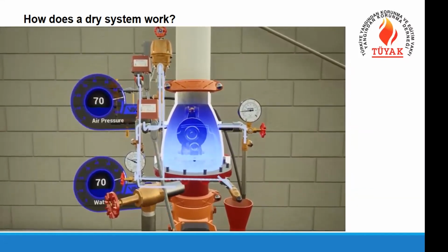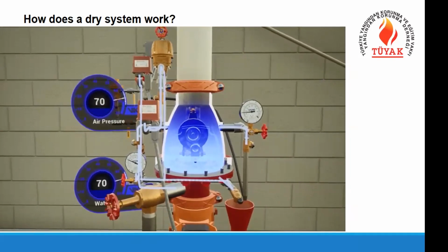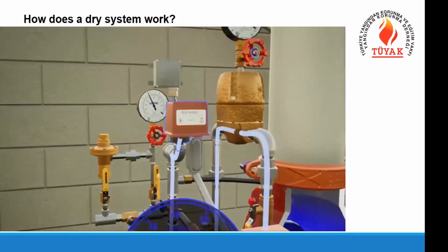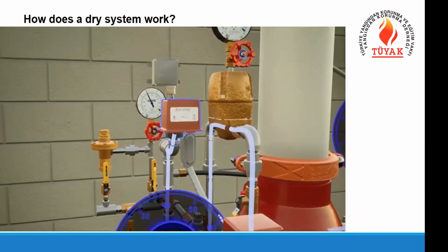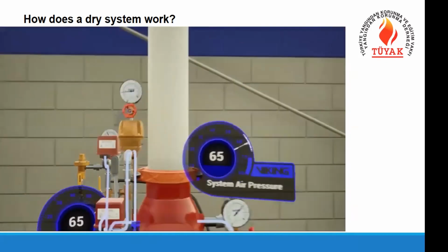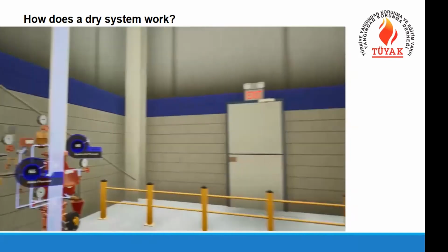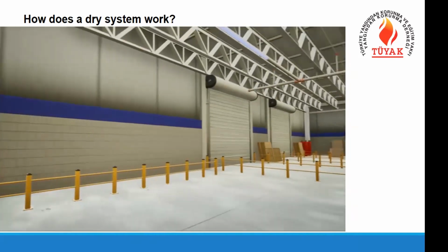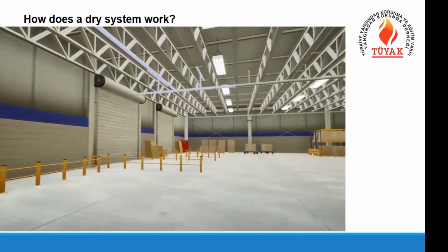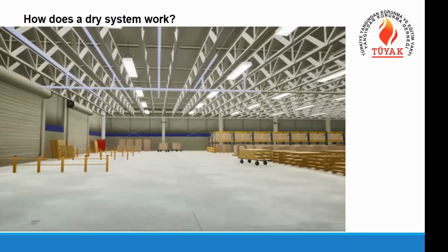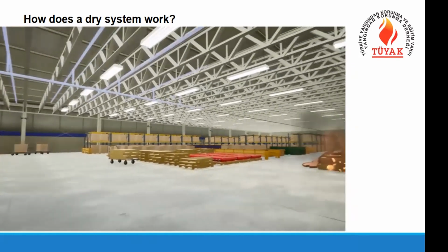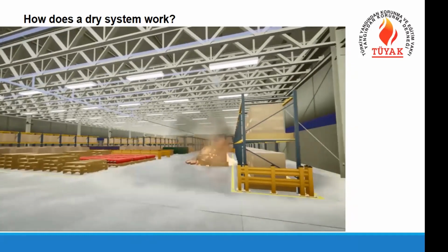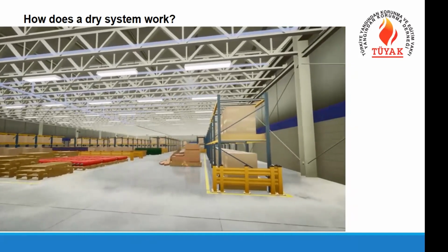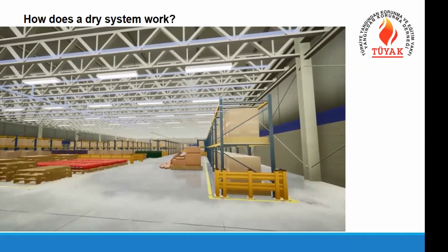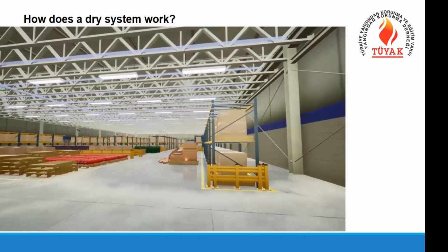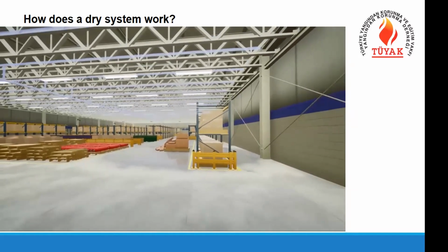Water flows through the valve and trim piping. The water flow alarms are activated. Water flows through the system, taking the path of least resistance to the open sprinklers. Air pressure will remain trapped in the pipes that are not in the critical path to the open sprinklers. As time passes, water will displace the remaining air and the lines will fill with water. The sprinklers continue to control the fire until the fire department arrives.